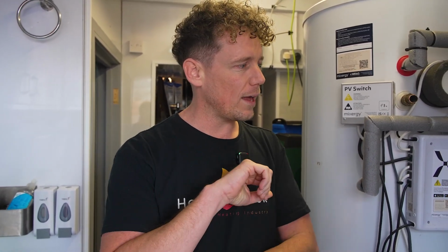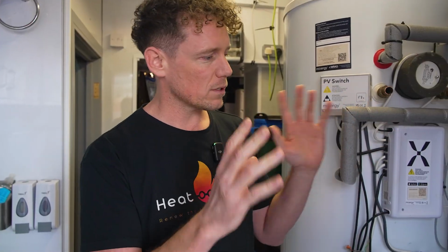And then once you've got it on, you just leave it, and then you're at the maximum efficiency you could ever want. Where it might get a bit hairy is where you've got rooms turning on and turning off. That's why I just leave everything on a very long running schedule. That's after watching your videos, actually. Yeah, that's what you do. You set the flow temperature as low as possible and then leave it on as long as possible, and then you're constantly feeding the thermal mass, which is the property.